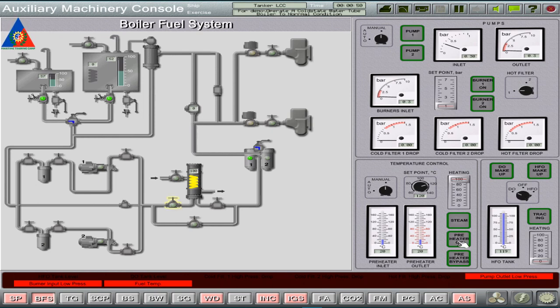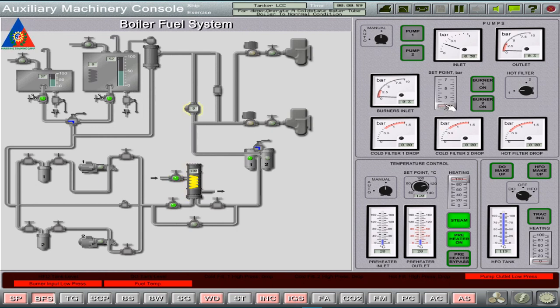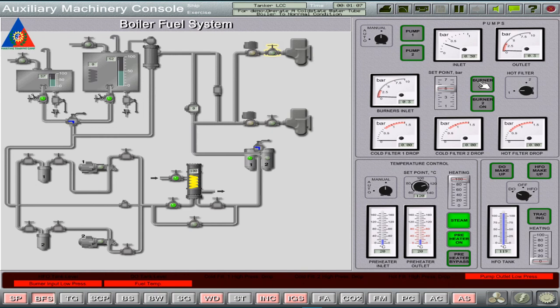We now line up the fuel system by opening the preheater and the steam inlet valves. Adjust the fuel feed pressure set point to 5 bars and open the burner number 1 and number 2 stop valves.